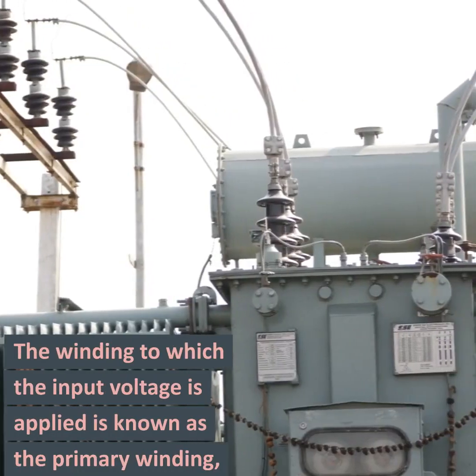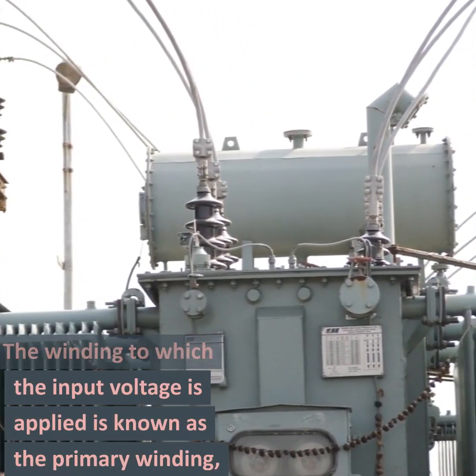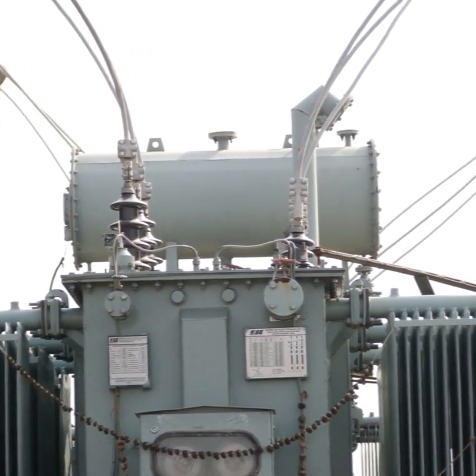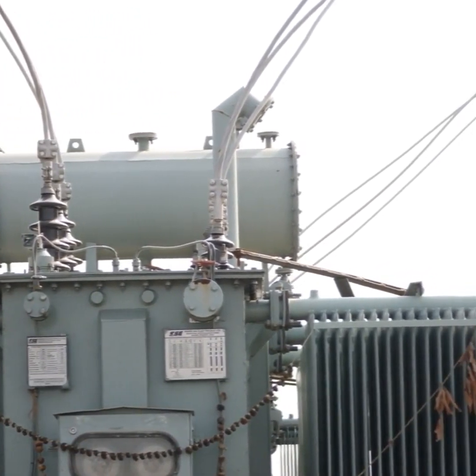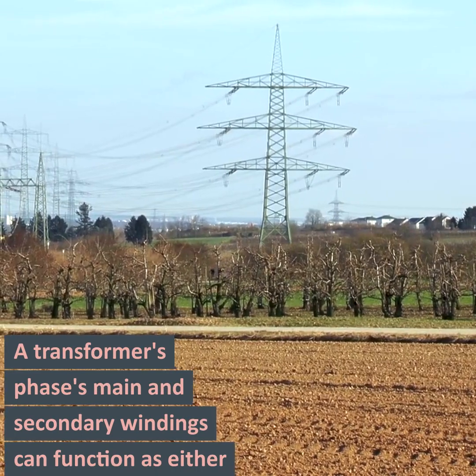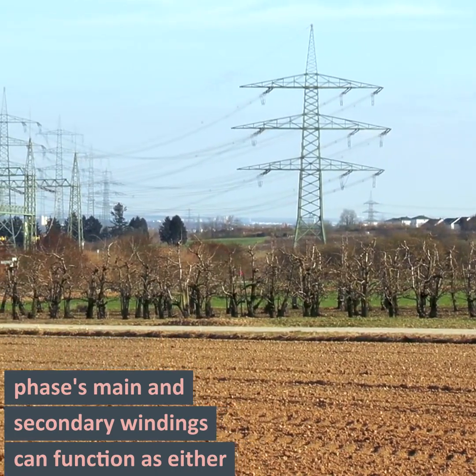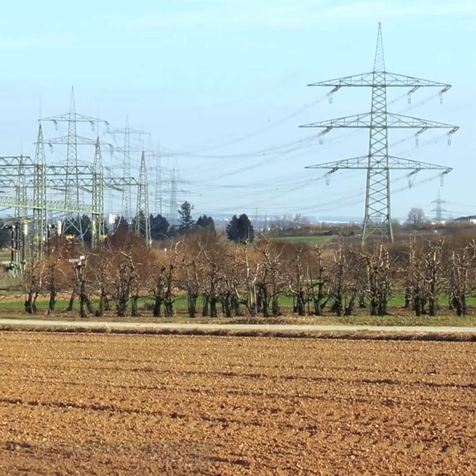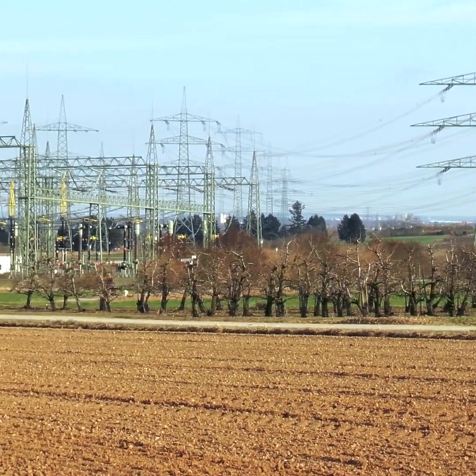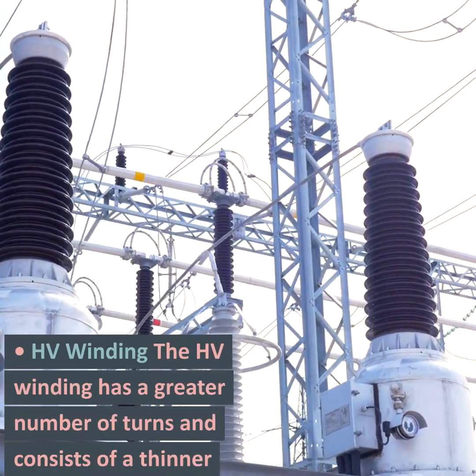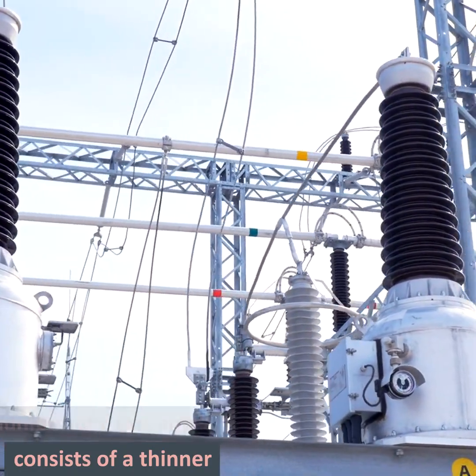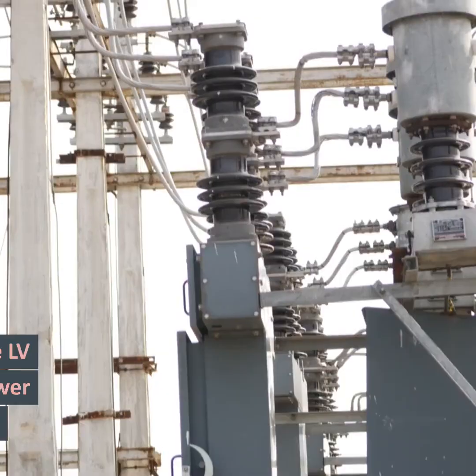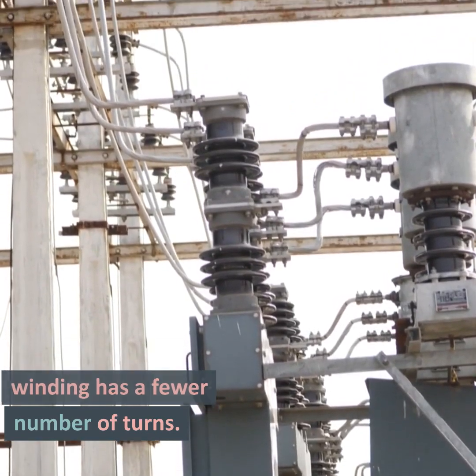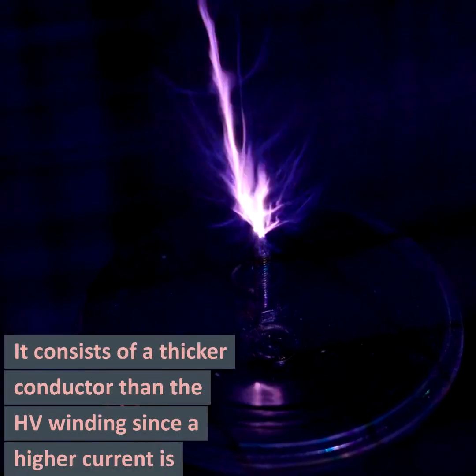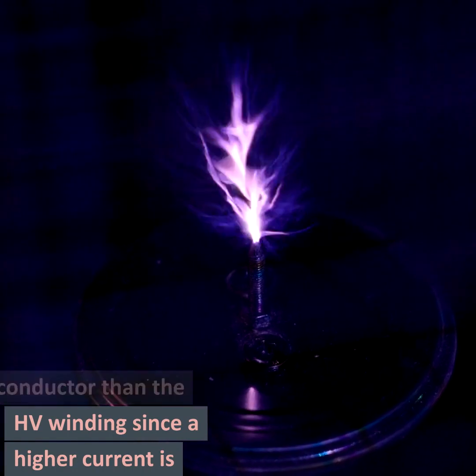The winding to which the input voltage is applied is known as the primary winding, and the winding to which the output voltage is supplied is known as the secondary winding. A transformer's primary and secondary windings can function as either the high voltage, HV, winding or the low voltage, LV, winding. The HV winding has a greater number of turns and consists of a thinner conductor than the LV winding. The LV winding has fewer turns. It consists of a thicker conductor than the HV winding since a higher current is carried in the LV winding.